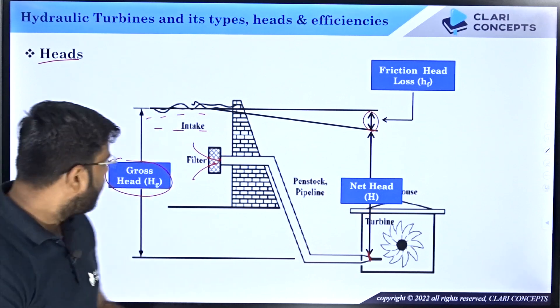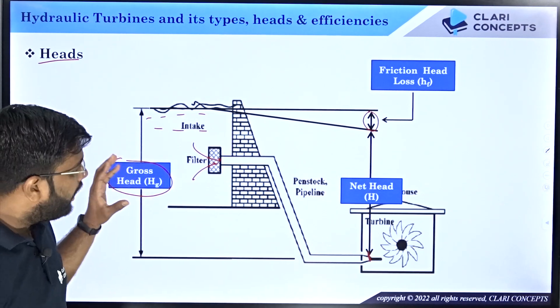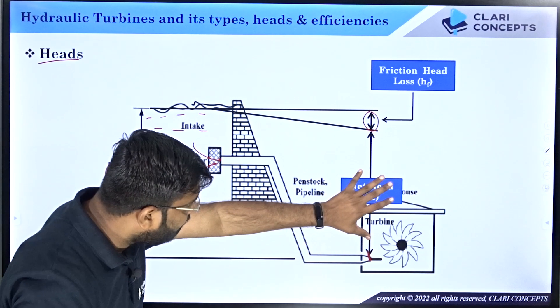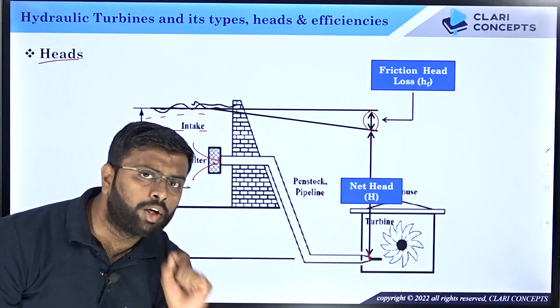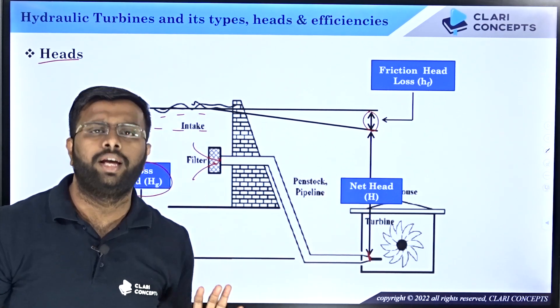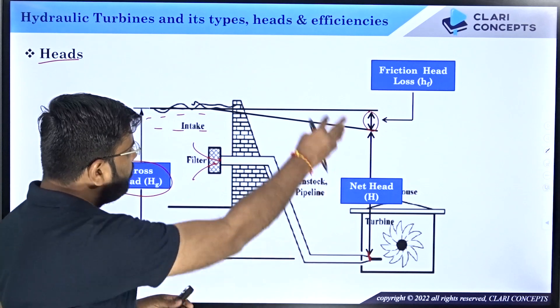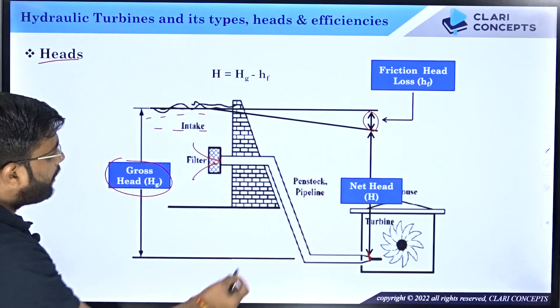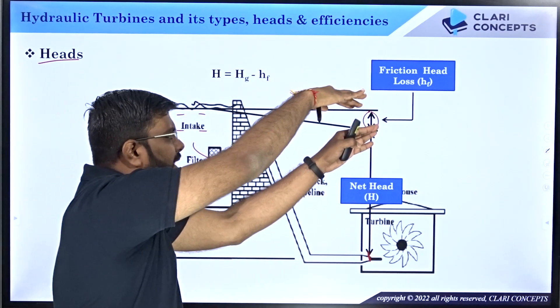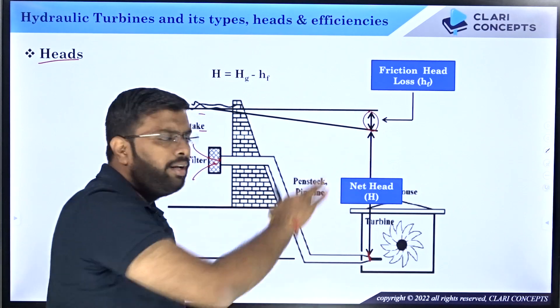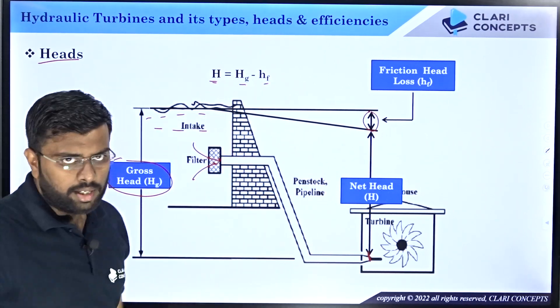So there are three heads: gross head, which is the total head available in your reservoir; net head, which is the head at turbine entry — the head available when water reaches the turbine; and friction head loss HF. So we can say that net head H equals gross head HG minus friction head loss HF.